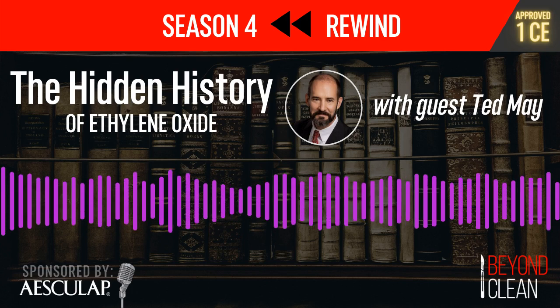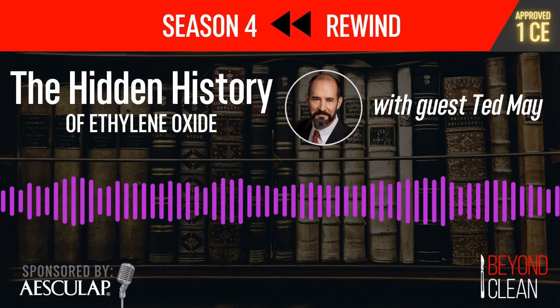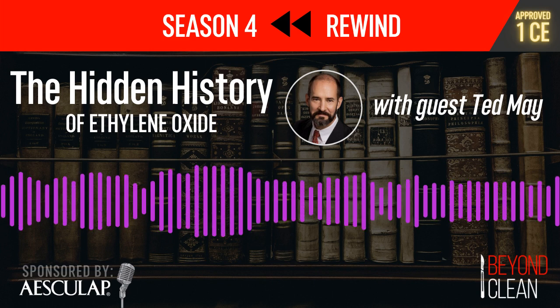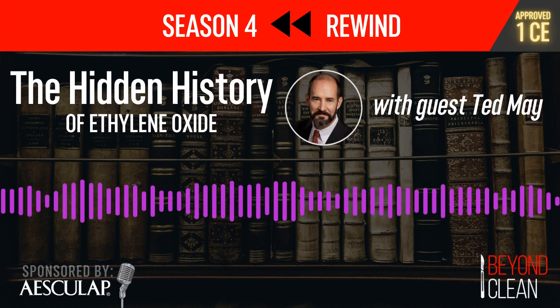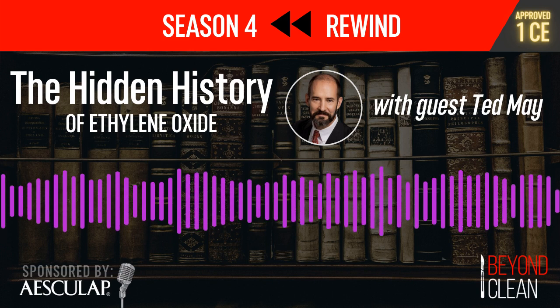Where an ethylene oxide sterilizer historically was built into a wall, with external compressors and fixed water lines, and typically a service room behind the sterilizers, modern ethylene oxide sterilizers are small tabletop systems that are easy to install. They're very space efficient, and it's a very different technology from what people using the ethylene oxide sterilizers of the 80s and 90s remember.